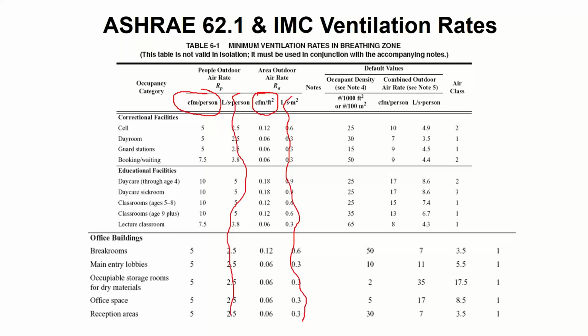So I've got to ventilate for the people and for the building. If I take a typical office space on the current codes, this is for all the ASHRAE. And this table applies to ASHRAE and IMC, and it has not really changed since 2006. So pretty much every state is on this version now. Or they're on different versions, but this part of the table is the same.